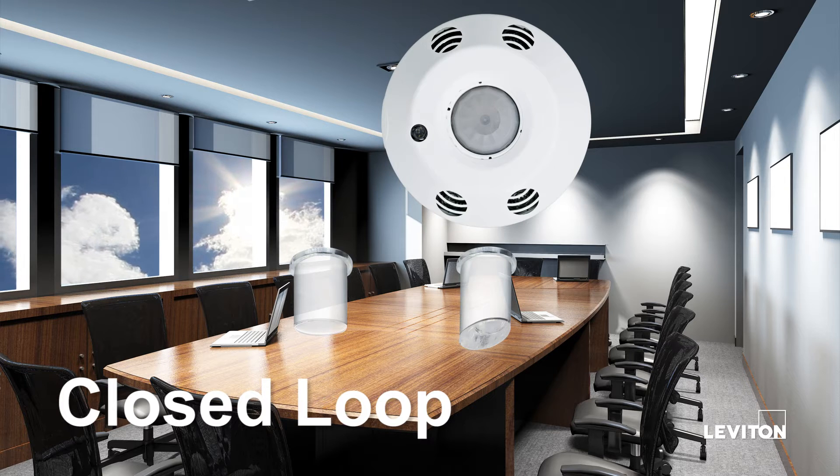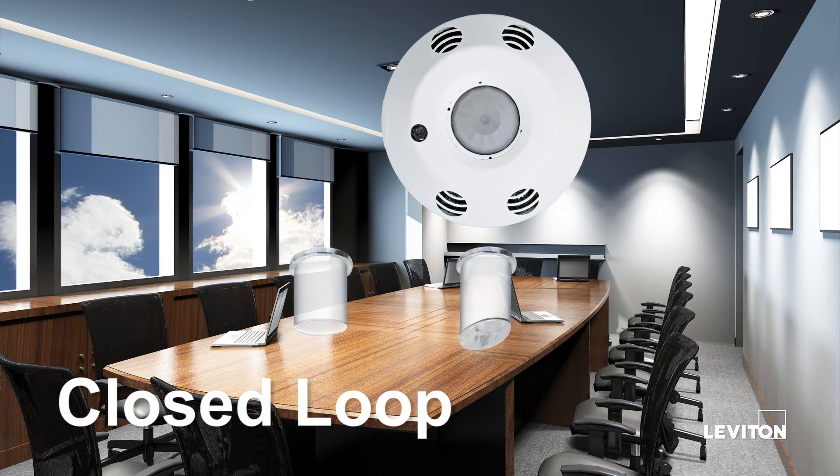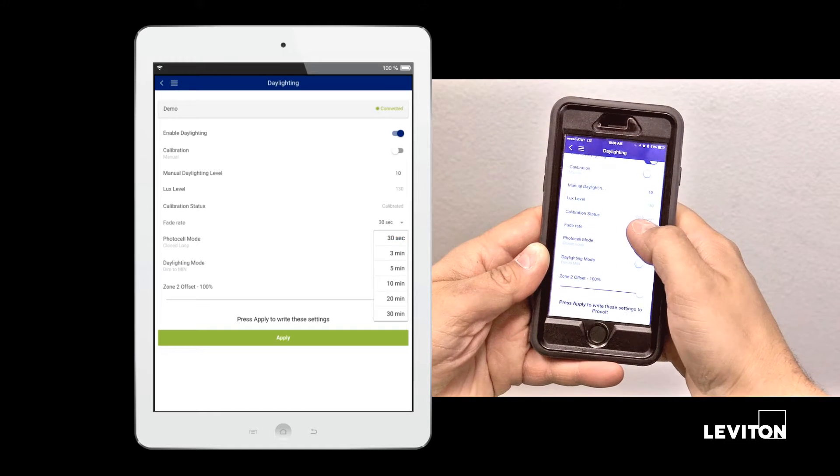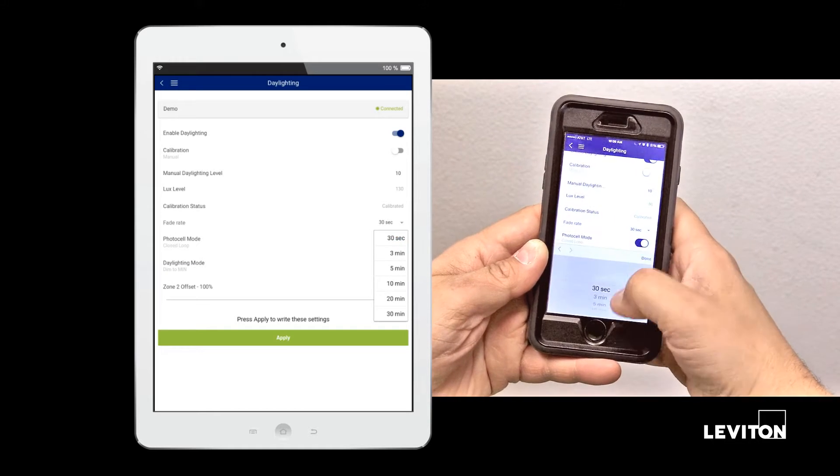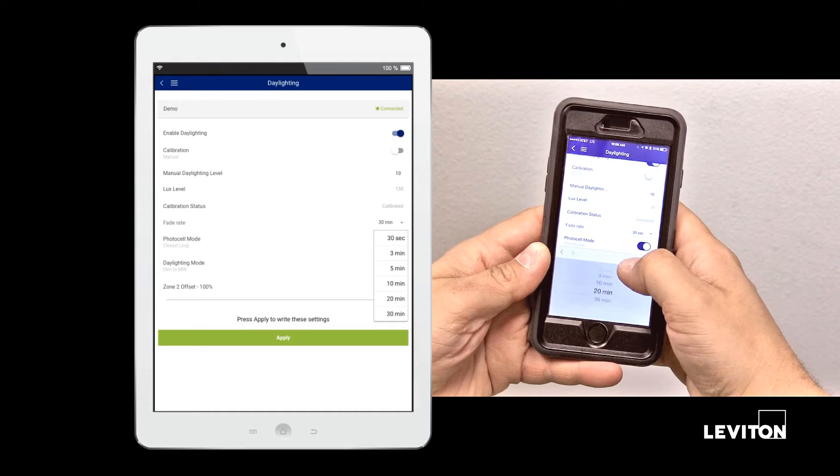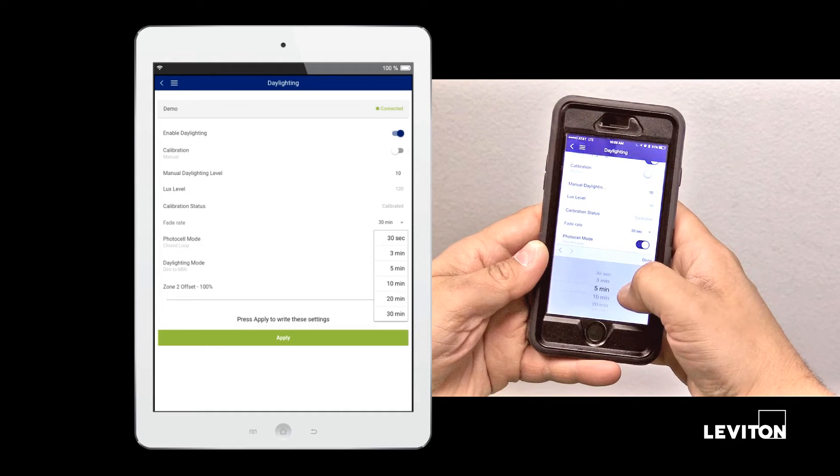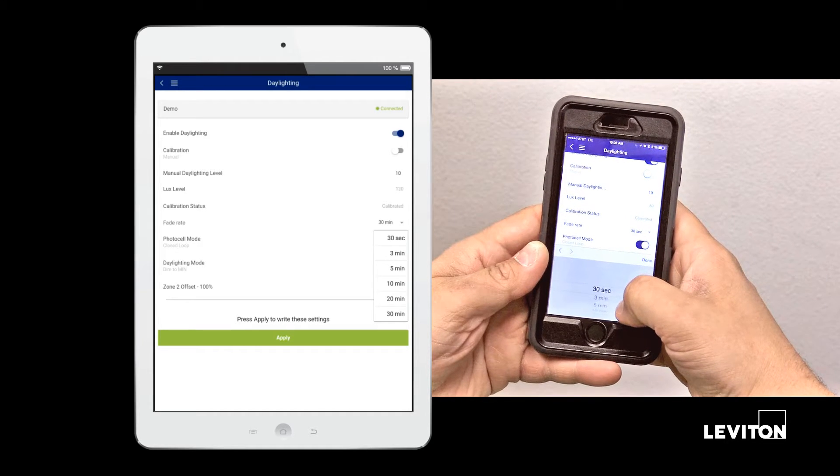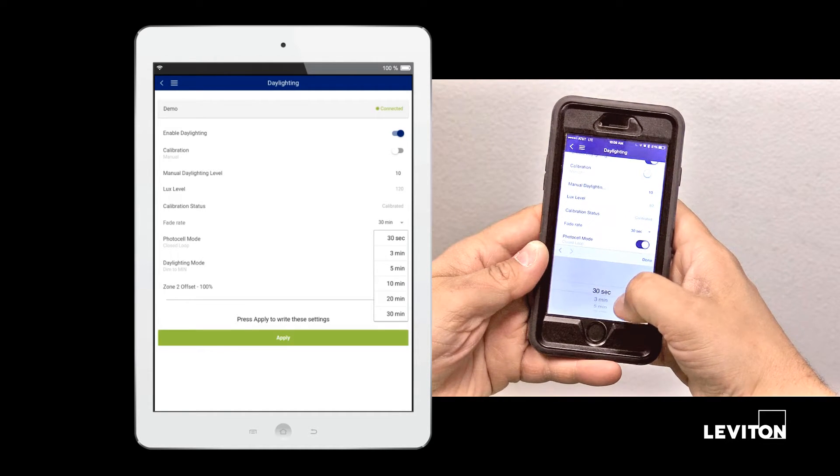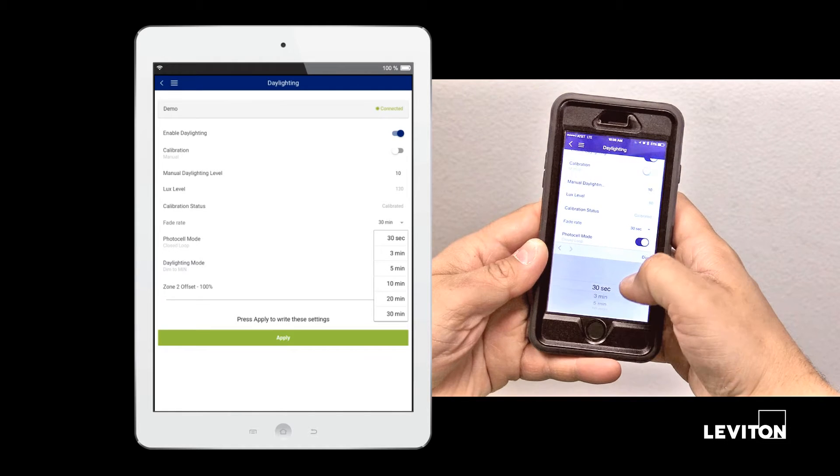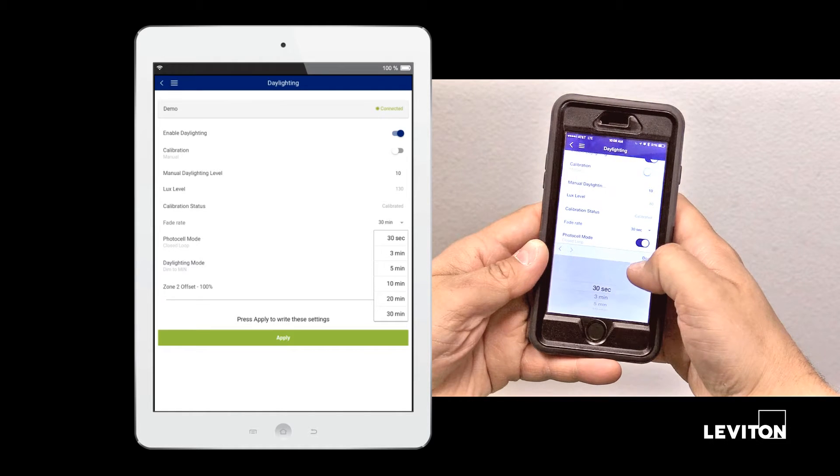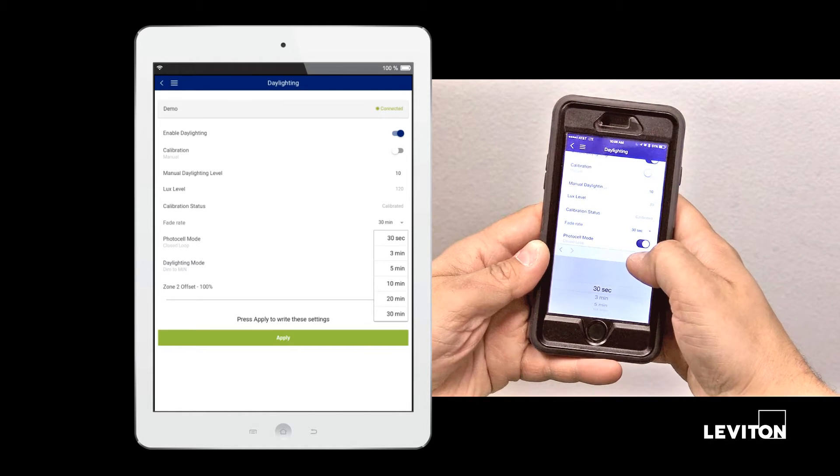angled light pipe directed towards the work surface. Set your fade rate from 30 seconds to 30 minutes. This sets the fade time for any change in light level. A longer fade rate reduces the end user's perception of lighting level changes.